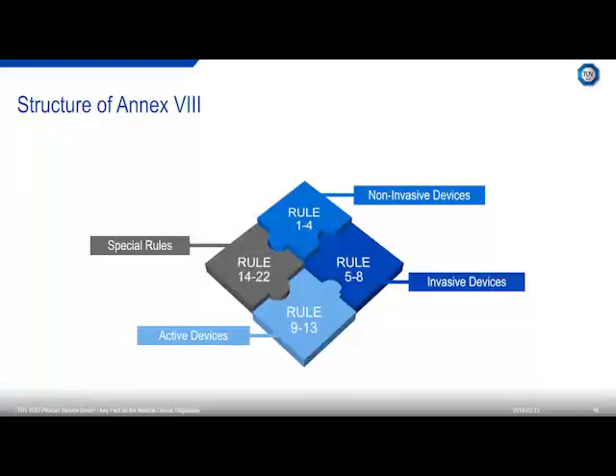The structure of Annex VIII is known from the current regulations. We have Rules 1 to 4 for non-invasive devices, Rules 5 to 8 for invasive devices, Rules 9 to 13 for active devices, and the special rules for special devices, which are Rules 14 to 22. What you typically do is, if you have your medical device, you have an intended purpose. With this intended purpose, you go through Rules 1 to 22, and wherever you end up in the classification, that's your device. This can be taken as a flowchart, and I've seen some flowcharts out there that can be used to classify your device.